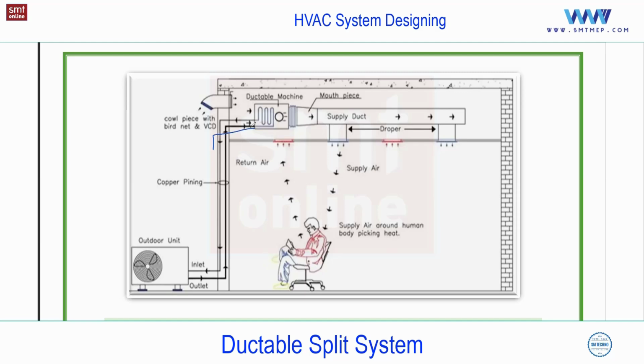Why? Because this drain water is chilled water, no? And if it is running inside this pipe which is above the false ceiling, what will happen? On the surface of that pipe, you will find the temperature less than or equal to the dew point temperature. So there is condensation at the surface, no? So what will happen? The droplets of water are going to fall on the false ceiling or on the electrical items, so that may create a short circuit or damage the false ceiling.